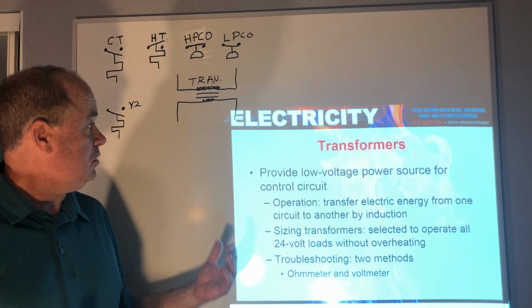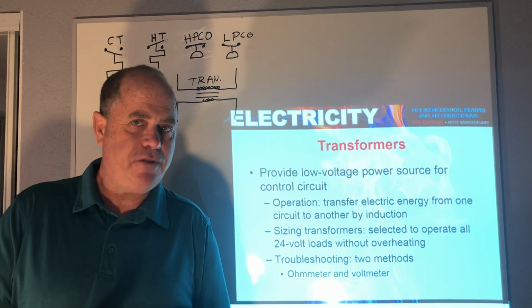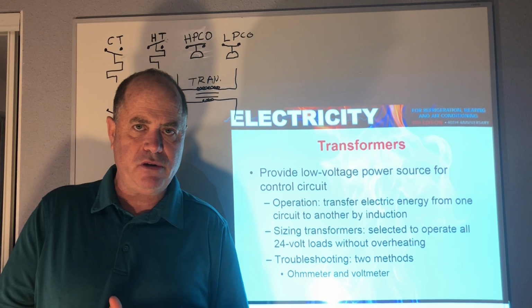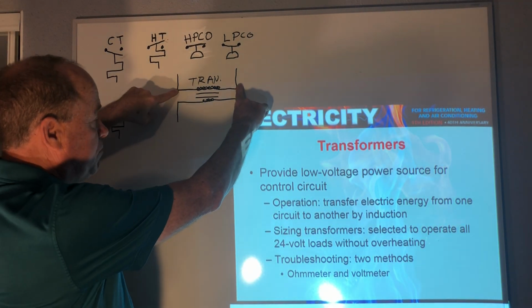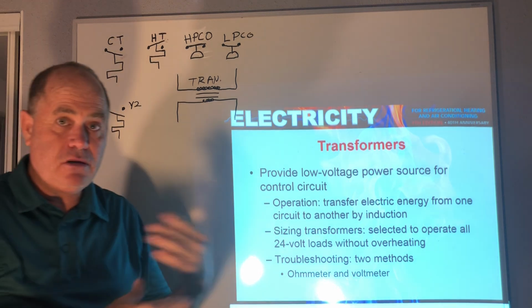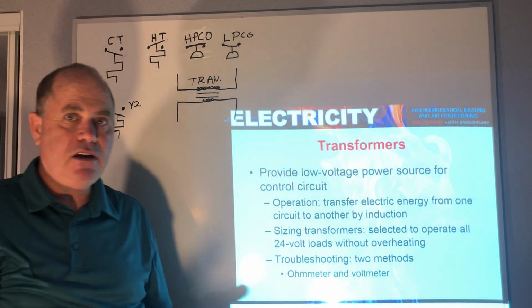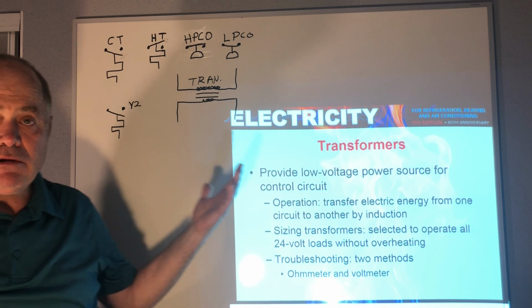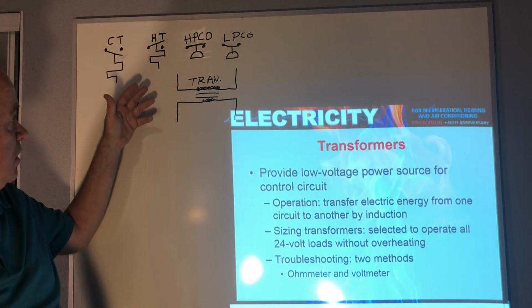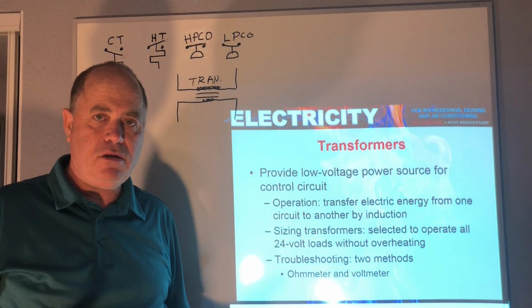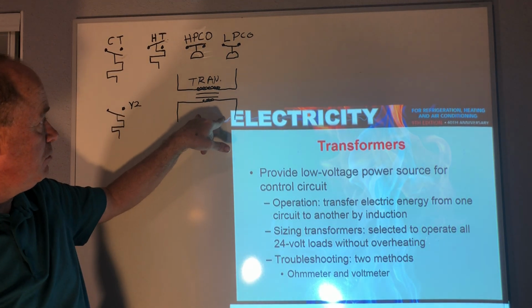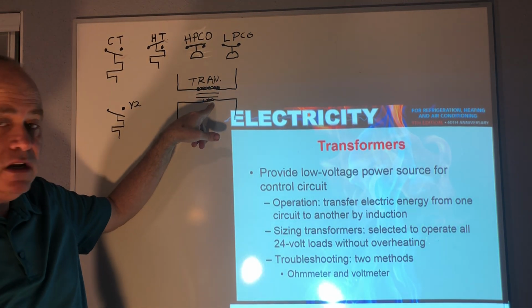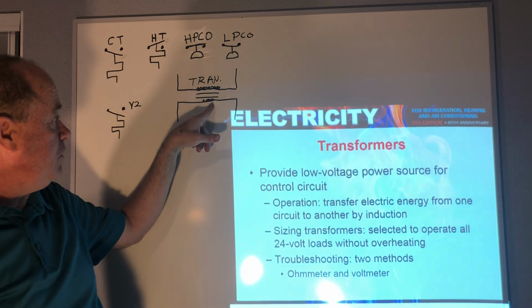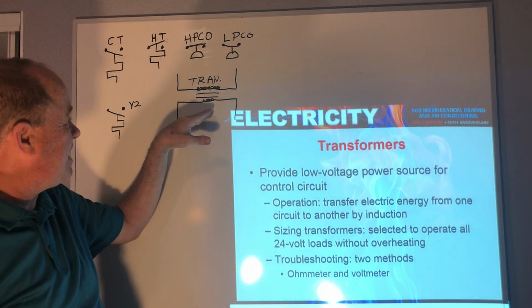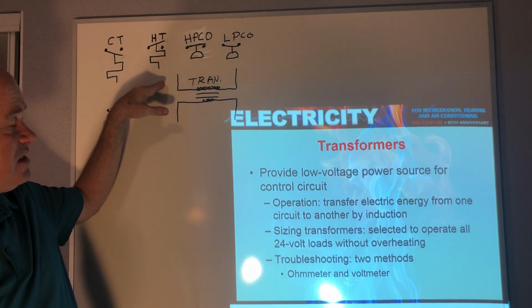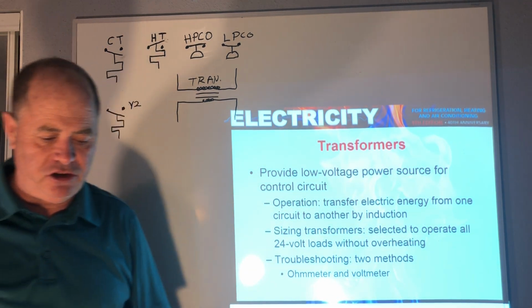And that's using the voltmeter, but you can also verify your diagnosis if you think it's a bad transformer by taking the resistance here in the primary, which should be a measurable resistance. It shouldn't be zero, it shouldn't be infinite or a billion ohms. It should be a measurable resistance, 20, 30, or whatever ohms. It could be more or a little bit less. And then some measurable resistance in the secondary. It shouldn't be burned open, an open lead or infinite. It should be measurable. And the secondary resistance is always going to be less than the primary because we're stepping down the voltage.